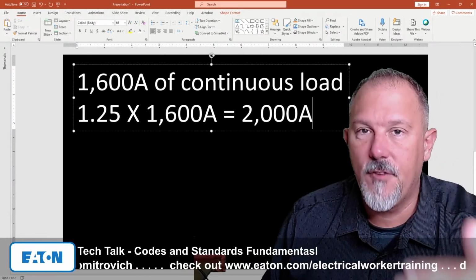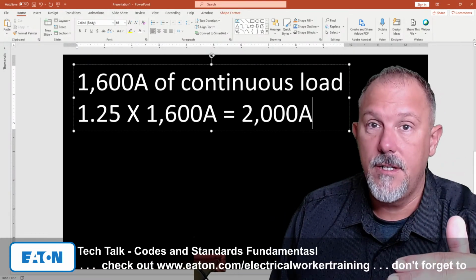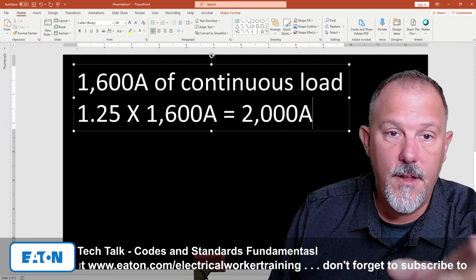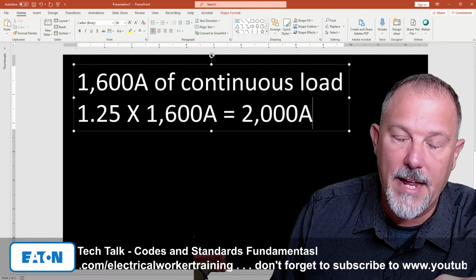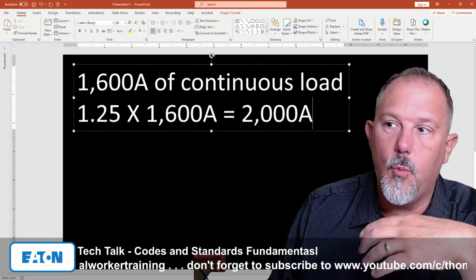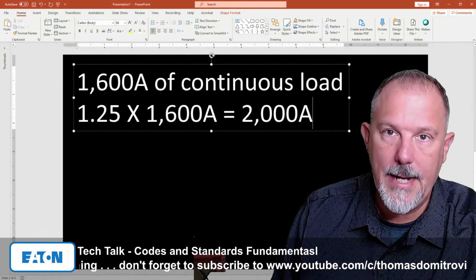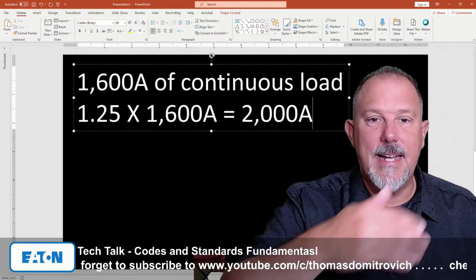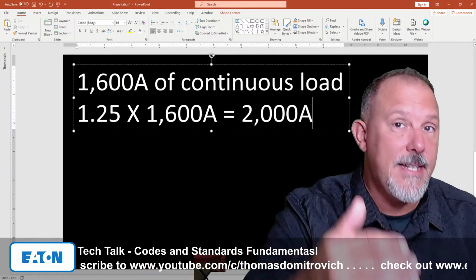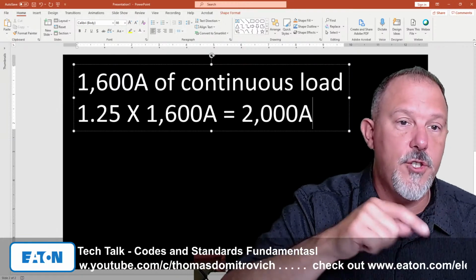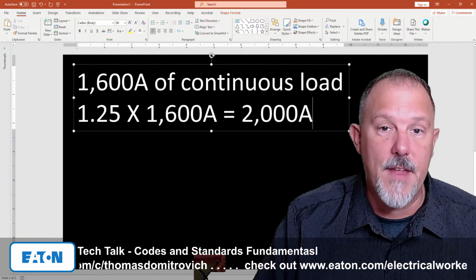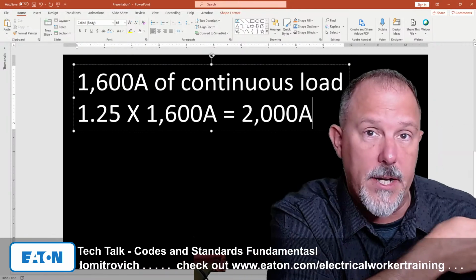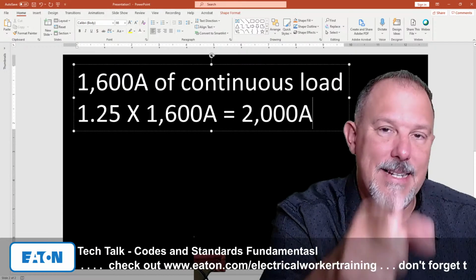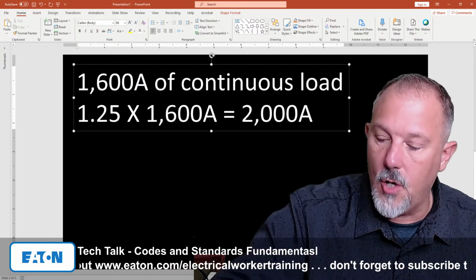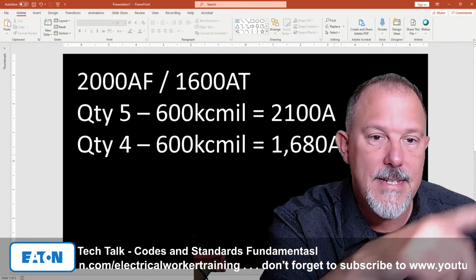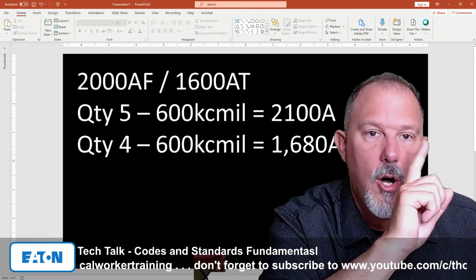Now, let's go back to this question. A 2000 amp frame circuit breaker is 25% larger than the 1600 amp continuous load. So what the question was related to is that I have a 2000 amp circuit breaker and 1600 amps worth of continuous load, and 1.25 times 1600 is 2000. I have a 2000 amp frame circuit breaker, but I'm only going to put 1600 amps worth of conductor. I'm only going to put 4 600 kcmil conductors on that circuit breaker.